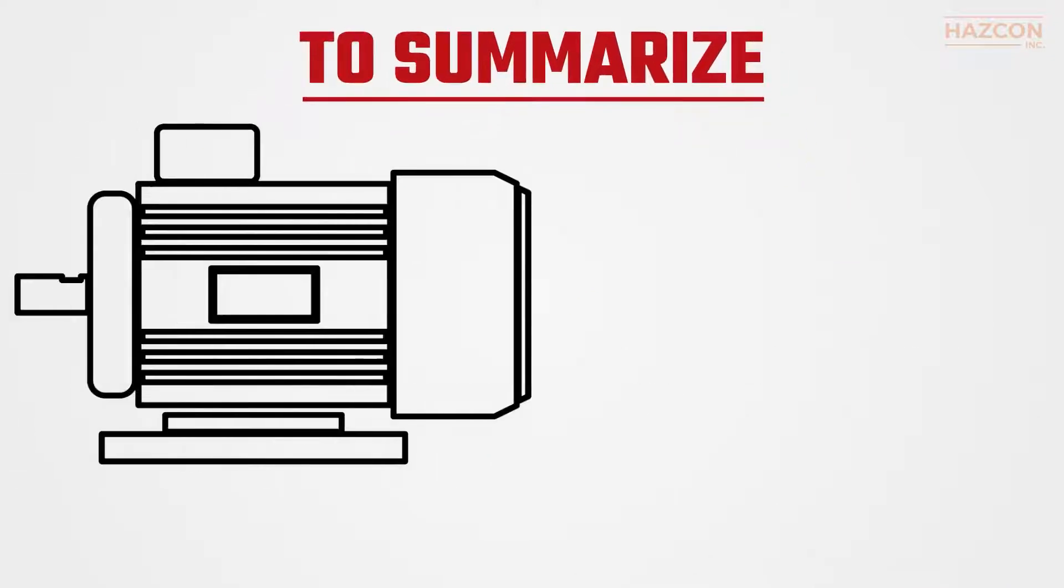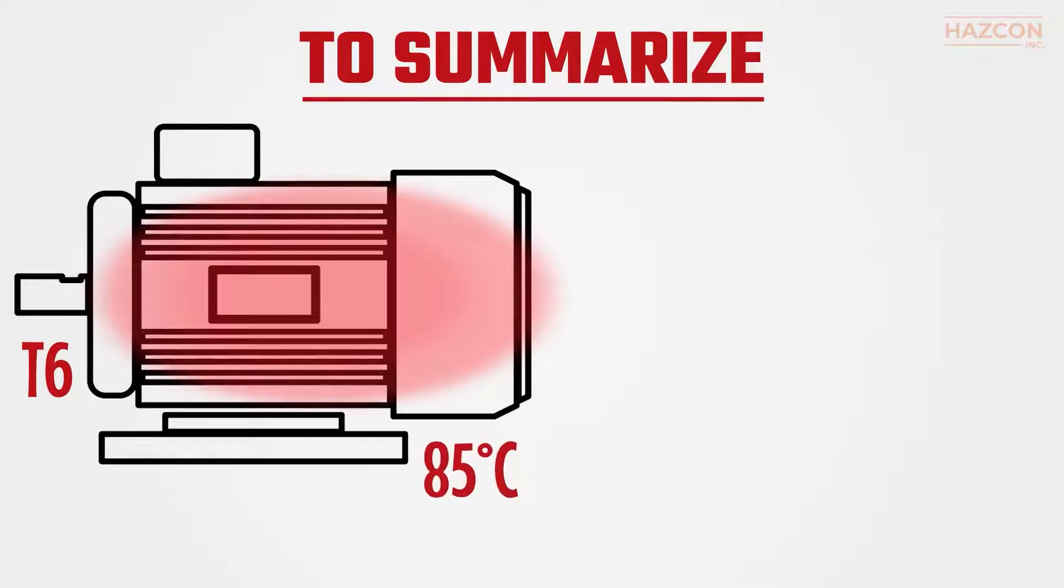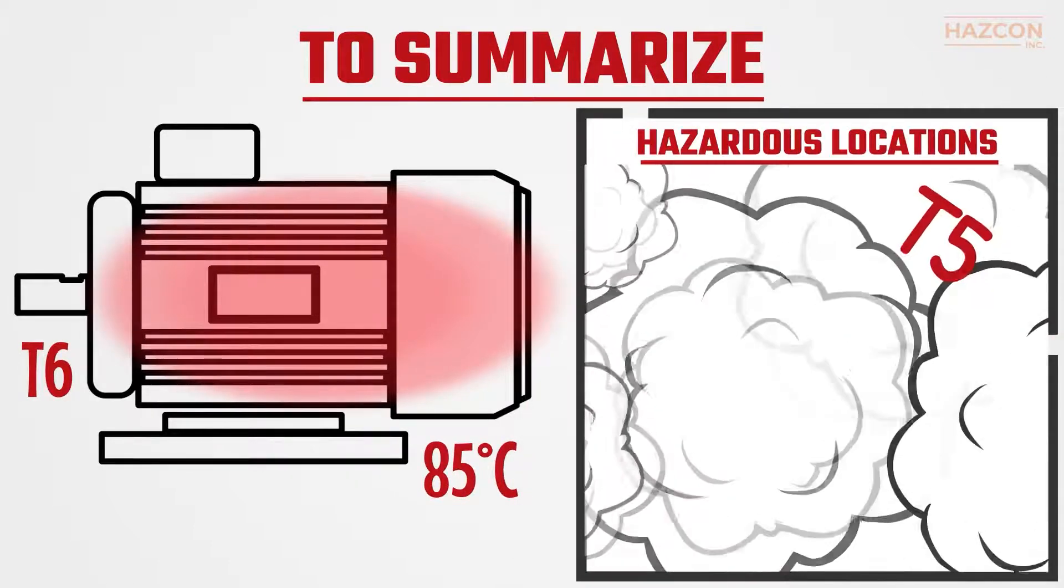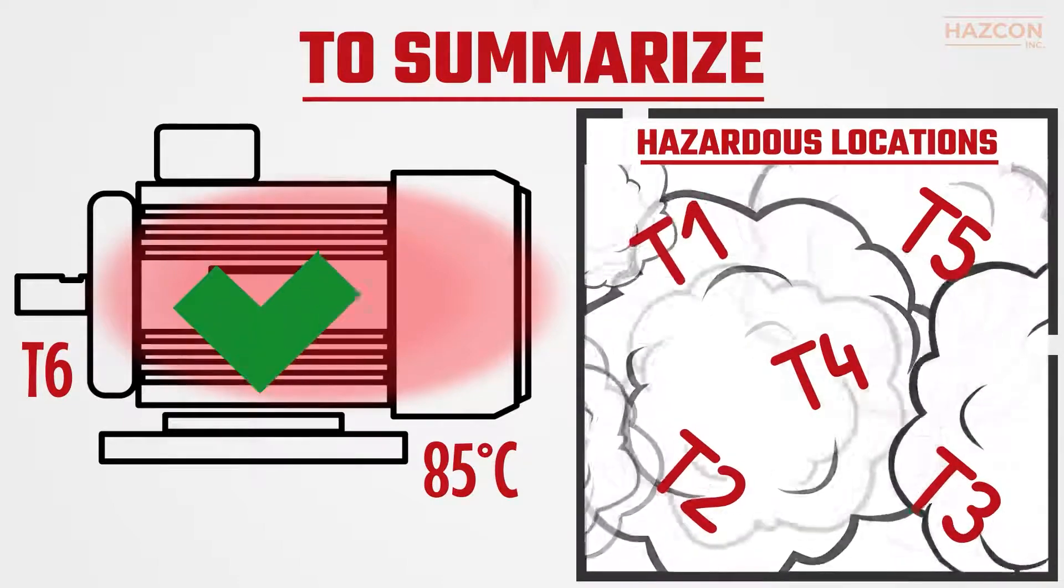All equipment with a T6 rating which has a maximum surface temperature of 85 degrees Celsius can also be used in T5, T4, T3, T2, and T1 environments.